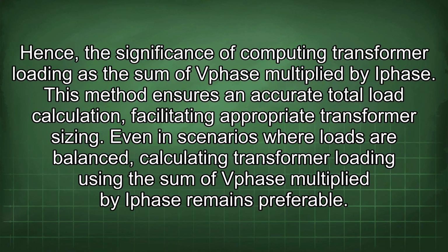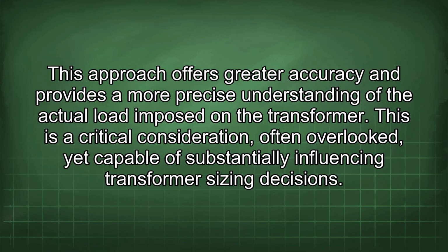Hence, the significance of computing transformer loading as the sum of Vphase multiplied by Iphase. This method ensures an accurate total load calculation, facilitating appropriate transformer sizing. Even in scenarios where loads are balanced, calculating transformer loading using the sum of Vphase multiplied by Iphase remains preferable. This approach offers greater accuracy and provides a more precise understanding of the actual load imposed on the transformer. This is a critical consideration, often overlooked, yet capable of substantially influencing transformer sizing decisions.